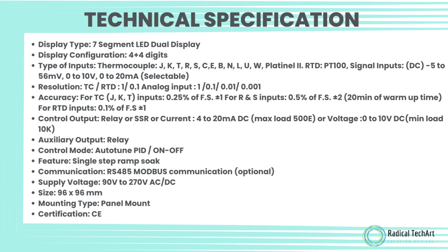Resolution: TC and RTD — 1 or 0.1; analog input — 1/0.1/0.01/0.001. Accuracy: for TC J, K, T inputs — 0.25% of FS ±1; for R and S inputs — 0.5% of FS ±2 with 20 minutes warm-up time; for RTD inputs — 0.1% of FS ±1. Control output: Relay, SSR, or Current 4 to 20 mA DC, max load 500Ω; or Voltage 0 to 10 V DC, min load 10KΩ.